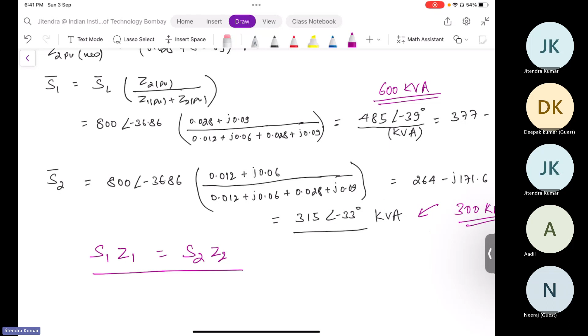And why is it happening? Both are not supplying in proportion to their kVA ratings because we have two transformers, and it is not satisfying the condition of parallel operation of the transformers. Necessary condition it is satisfying, but desirable condition it is not satisfying. It means S1 Z1 is not equal to S2 Z2. After the session you can calculate both the values and try to equate, and you will see that S1 Z1 is higher than S2 Z2. This is leisure time work you can perform now.